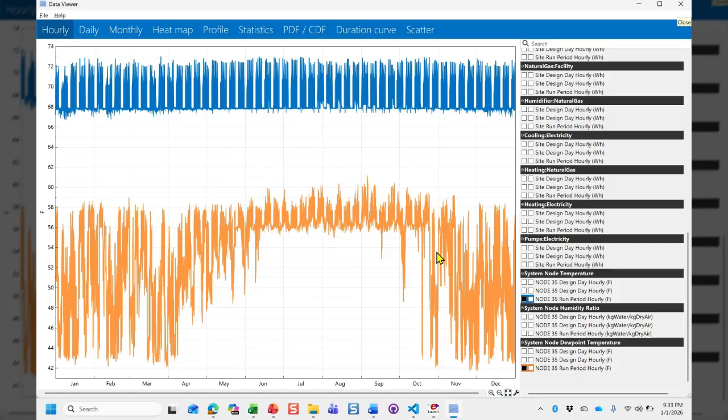So why would you do this, right? Here in a model, I had output not just cooling energy and heating. I had also output a specific point in my system to try and understand if the dew point was following my requirements. Up above, I'm showing the dry bulb temperature staying between 68 and 72, and then the dew point staying between 58 and 44, so trying to make sure I'm maintaining a level that I was aiming for in my controller.